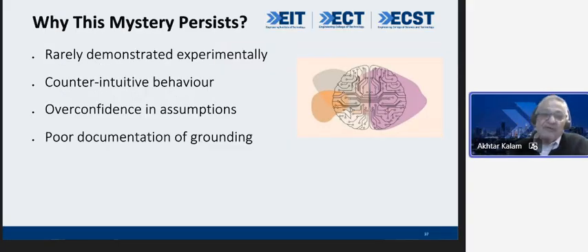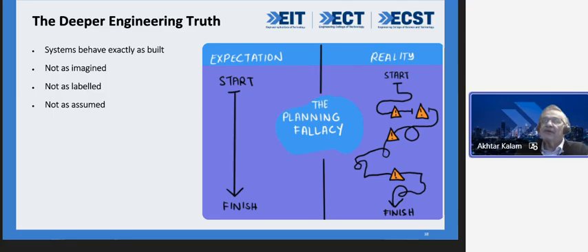Why does this mystery persist? Because you cannot demonstrate it experimentally. You can't do the behavior check. Overconfidence, when you think you know the solution and you don't have any documentation on grounding. Most of the time, you learn about Earth in your second year, and most of the time, you forget it. And often that is where the problem occurs. So, the deeper engineering truth, my friends, is that the system behaved exactly as it was built. It was not imagined, it was not labeled, it was not assumed. The system behaved exactly as it was designed.